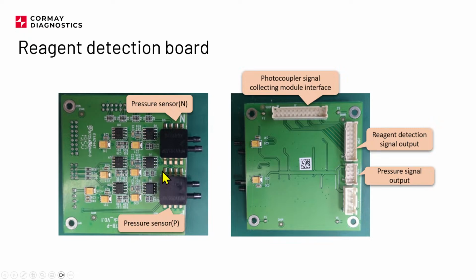But two pressure sensors, positive, negative. Sorry, negative, positive. This is the order. And photocoupler signals collecting modules interface. So those are the reagent detection signals from the reagent detector. So those are the photocouplers, right? So the optical principle is that the analyzer is checking if there is liquid in the line or air in the line, in the tubes, basically.